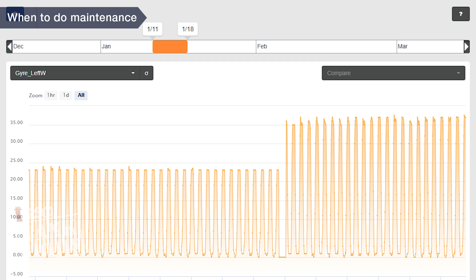I think most of us would prefer an actual method of measurement so we can change it when the performance falls below a predetermined level, like a 10, 20, or even 50% reduction in flow. At first glance, that may seem hard to do, but indirectly, I think there's a pretty easy solution using power monitoring on some of the more advanced controllers. For example, on the BRS-160, when the gyres get dirty, there's a very noticeable drop in flow, which I can identify visually in all the ways that we discussed, but there's also a drop in power consumption as the pump head spins slower. Once we disassemble and clean them, the power and the flow rise back up to normal, meaning that we can set up a pump maintenance alarm if the power draw ever falls below, say, 70% of normal output, letting us know it's time to perform general maintenance.